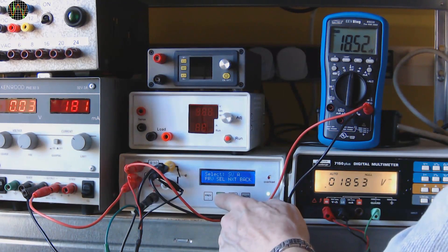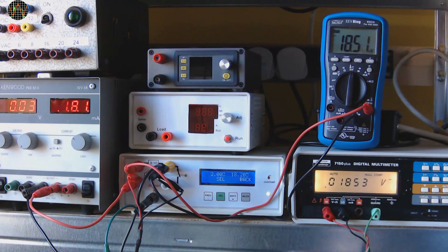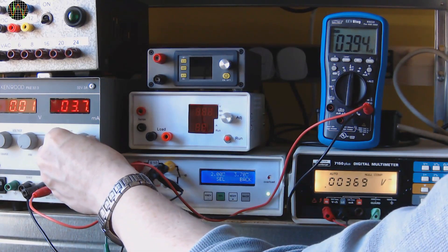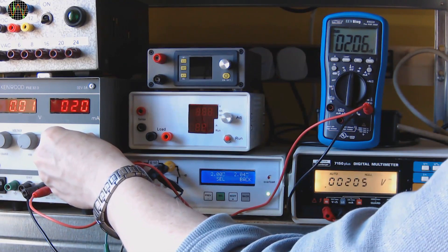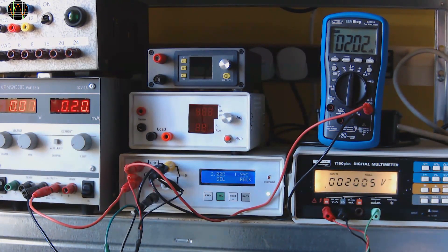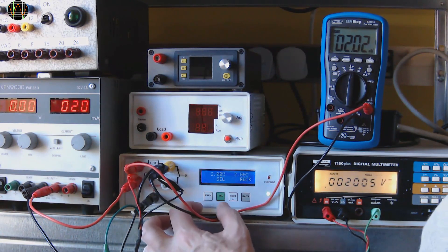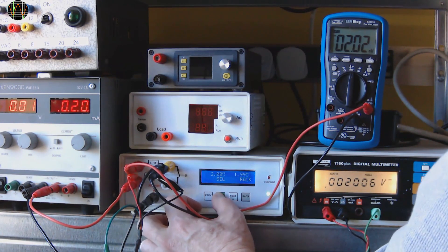The target displayed on the upper left of the power monitor display is 2mV. Now I adjust the current until I see 2mV on the Solartron. And press SEL to move to step 2 and the new target of 38mV.